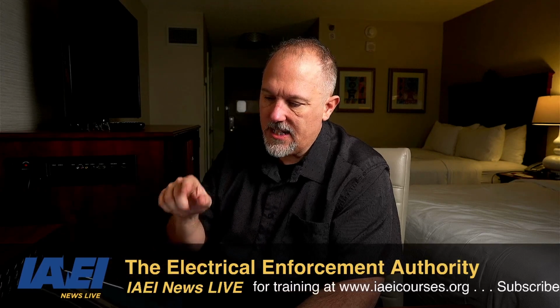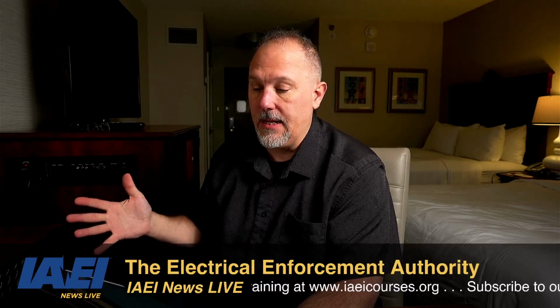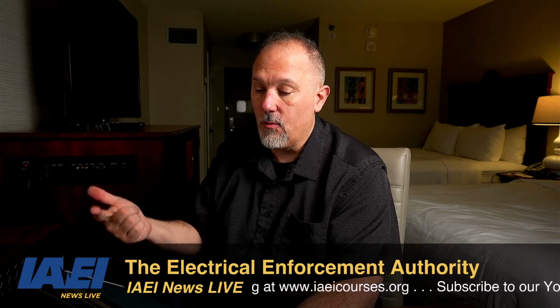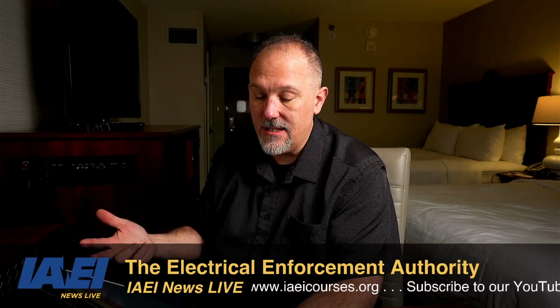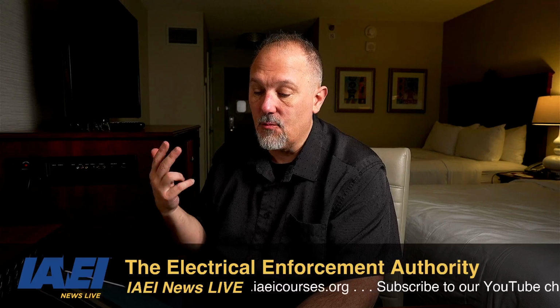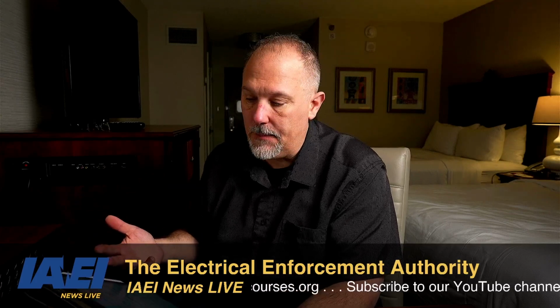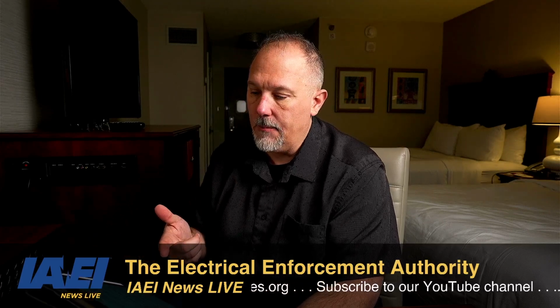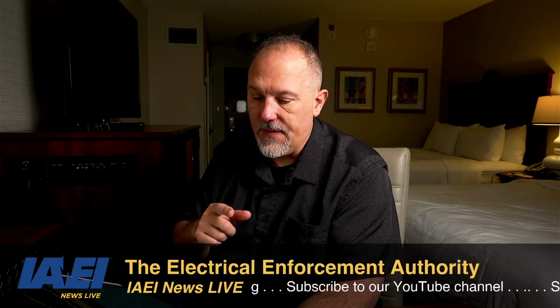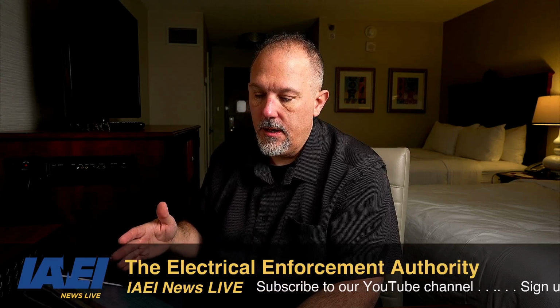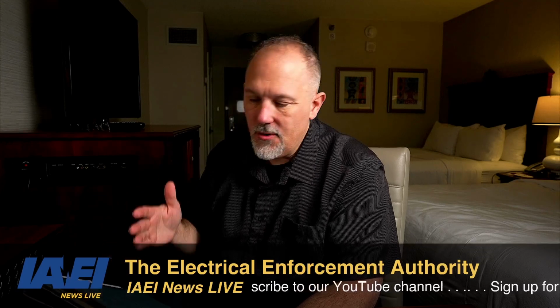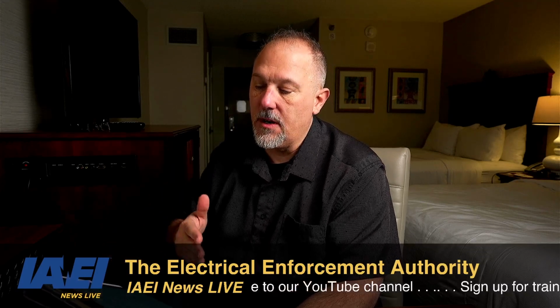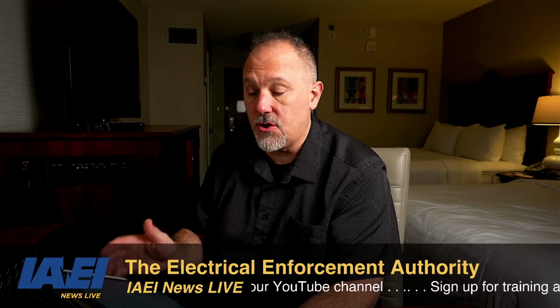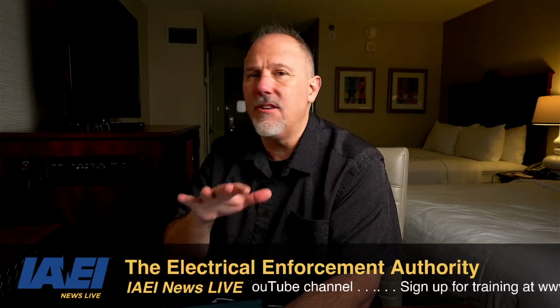Each generator has to be provided with an accessible nameplate, giving the manufacturer's name, rated frequency, the number of phases if it's AC, the rating in kilowatts or kilovolt amperes, power factor, the normal volts, and amperes corresponding to the rating, and the rated ambient temperature. So that's information that, as long as you have a listed product, is going to be there.